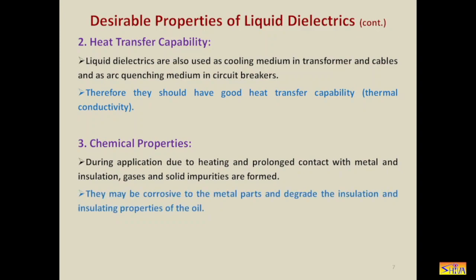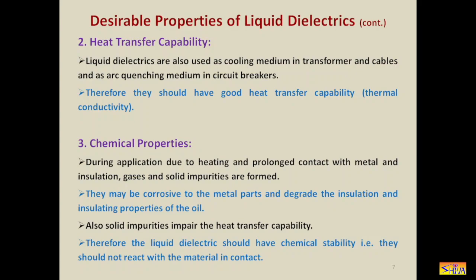They may be corrosive to the metal parts and degrade the insulation and the insulating properties of the oil. Also, solid impurities impair the heat transfer capability of the liquid dielectric. Therefore, the liquid dielectric should have chemical stability, that is, it should not react with the material in contact.